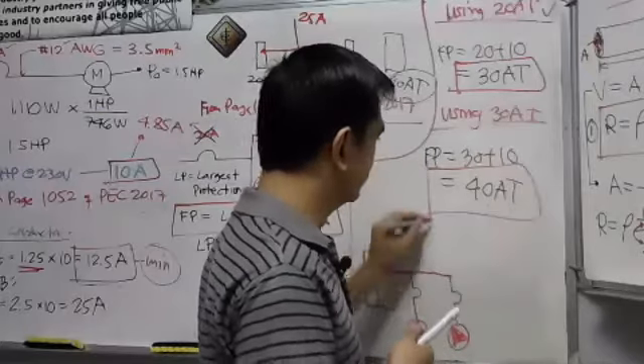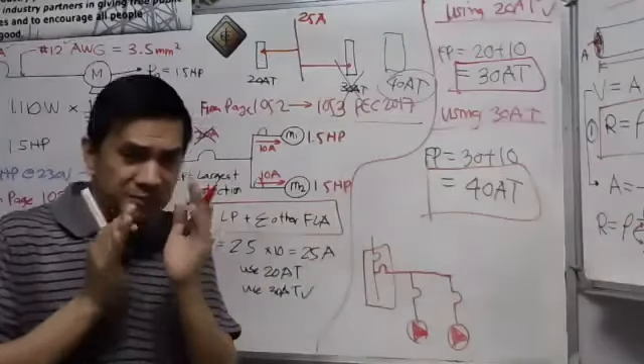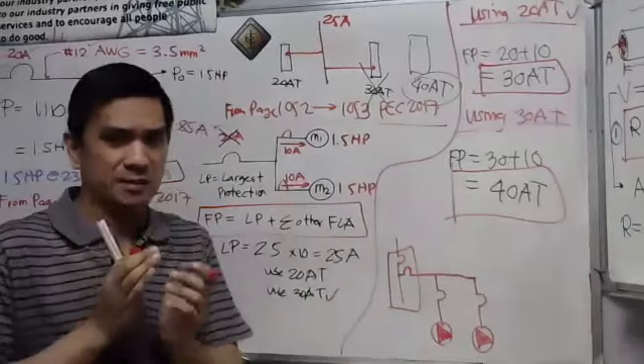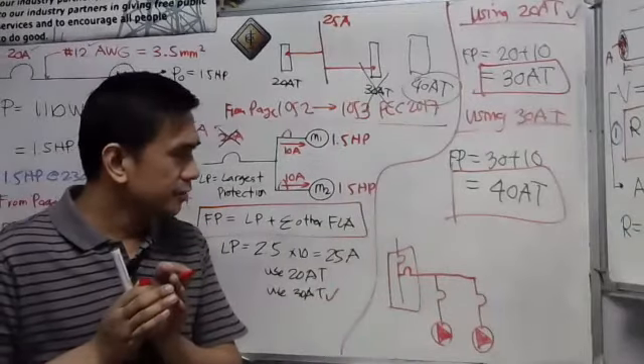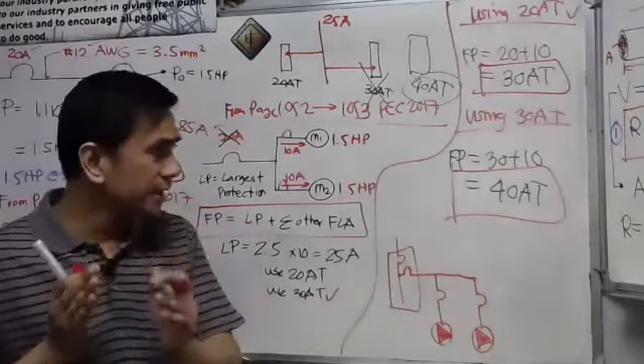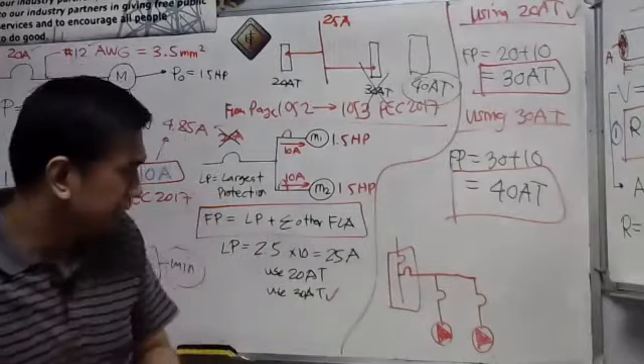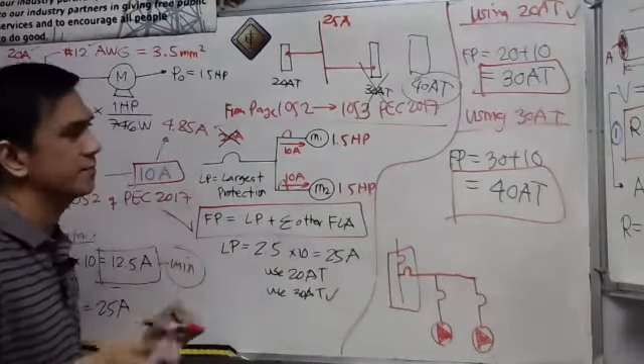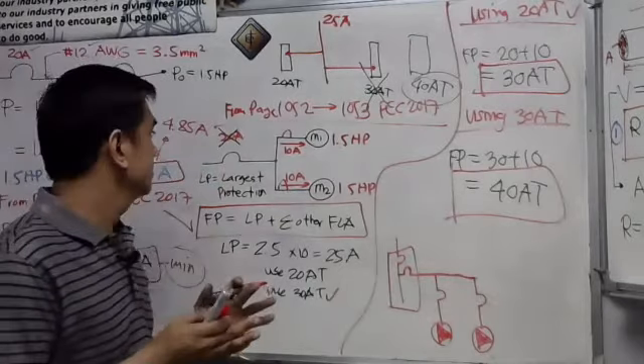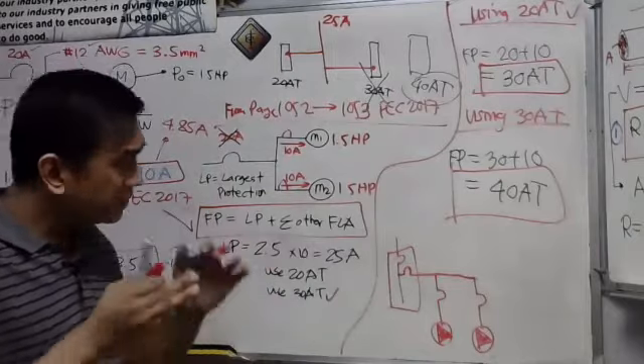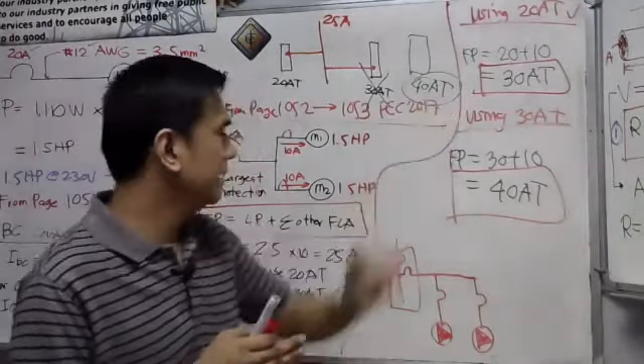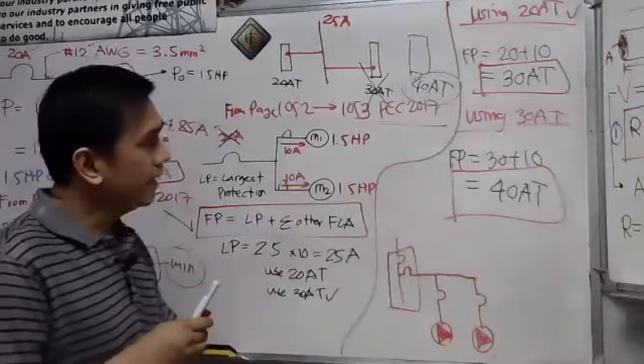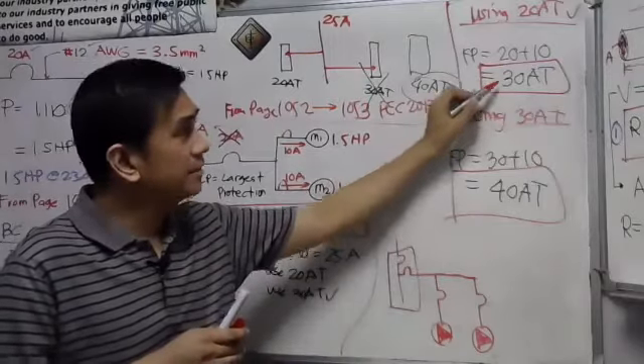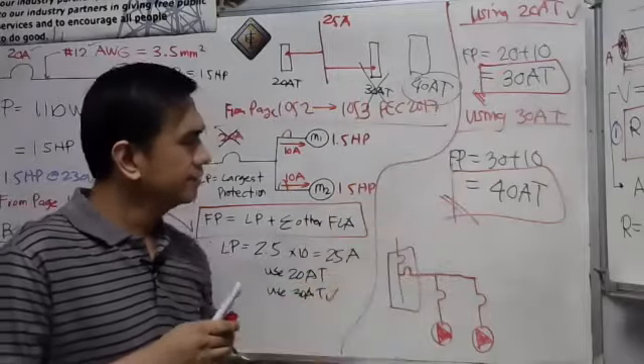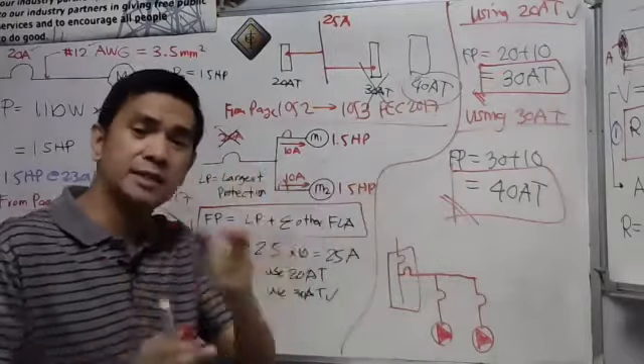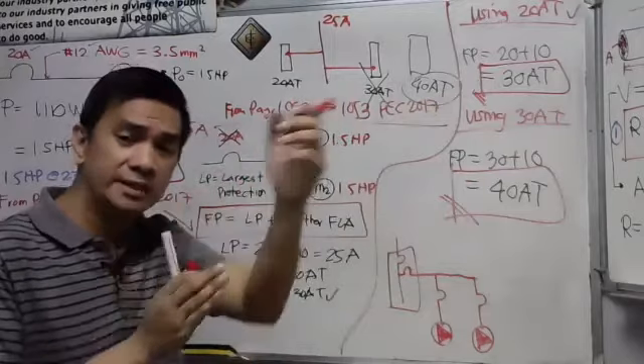Actually, guys, this is not a licensure exam question, no? But you will learn something from here. It can be used in the licensure exam. Maybe this is not a copy paste, no? It's not exactly like that, but you will learn something that can also be used in the licensure exam. Just like this formula, of course. So, more or less, the circuit breaker minimum is the 30 ampere. Well, we can have the 30 as the minimum. Then the maximum is the 40. Although in the code, it says if you are sizing the protection, that is already the maximum. No? If you are sizing the wire, that is already the minimum.